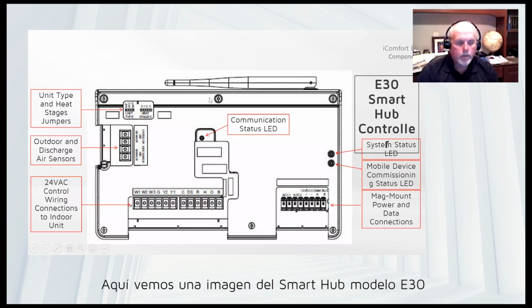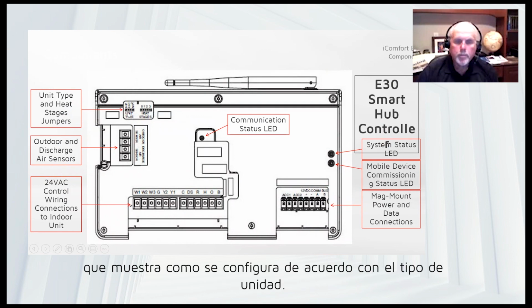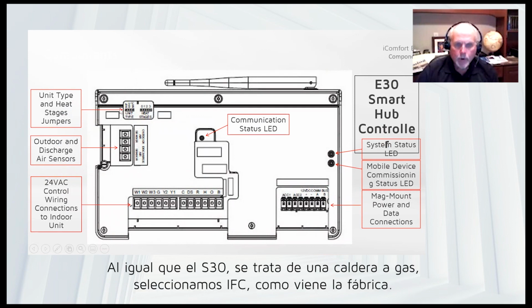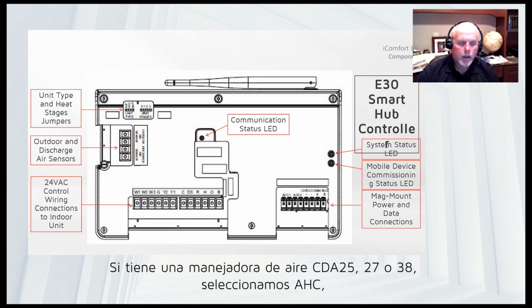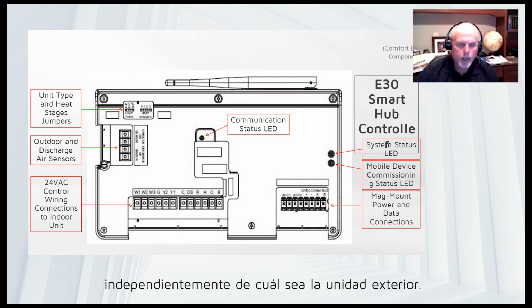And here is a drawing of the E30 Smart Hub. Here is where you set your unit type. Again, if a gas furnace is involved, it's IFC, which is how it comes to you from the factory. If you have an air handler, CDA 25, 27, or 38, then it will be on AHC, regardless of what the outdoor unit is.